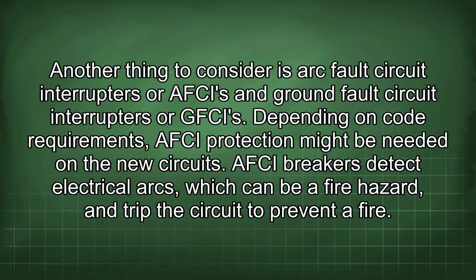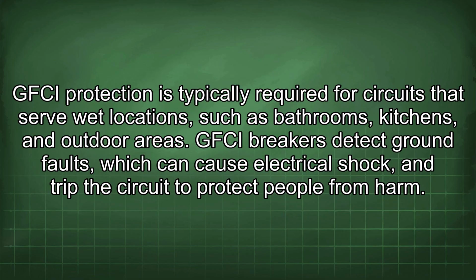Another thing to consider is arc fault circuit interrupters, or AFCIs, and ground fault circuit interrupters, or GFCIs. Depending on code requirements, AFCI protection might be needed on the new circuits. AFCI breakers detect electrical arcs, which can be a fire hazard, and trip the circuit to prevent a fire. GFCI protection is typically required for circuits that serve wet locations, such as bathrooms, kitchens, and outdoor areas. GFCI breakers detect ground faults, which can cause electrical shock, and trip the circuit to protect people from harm.